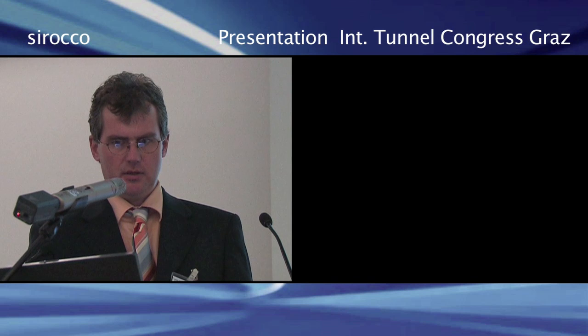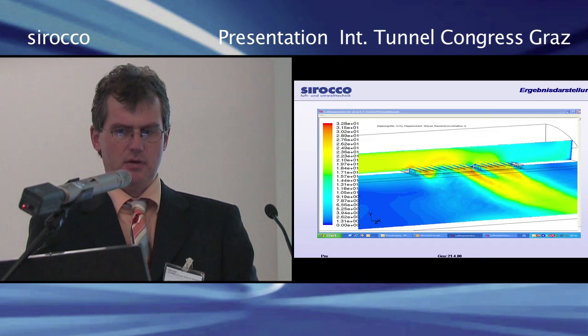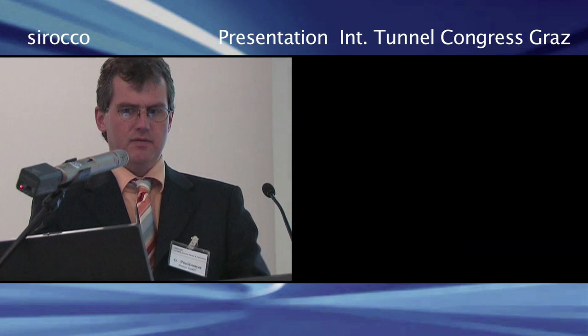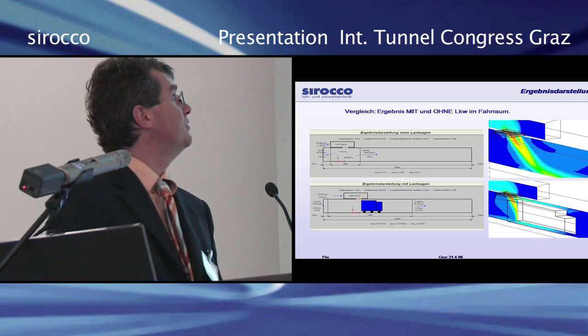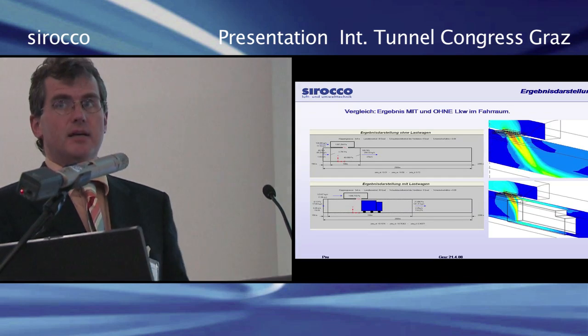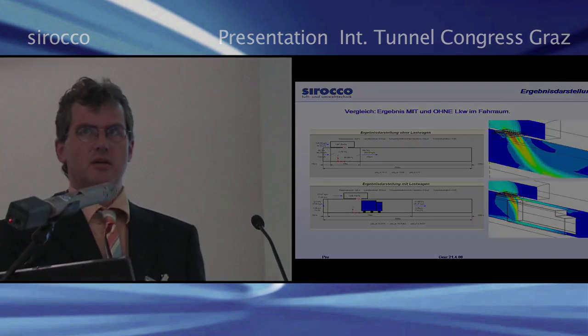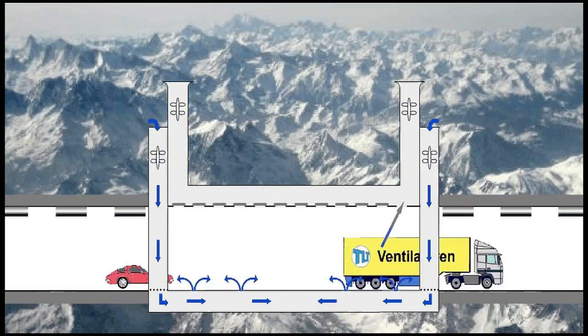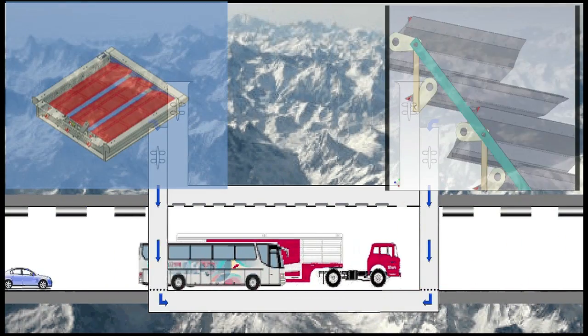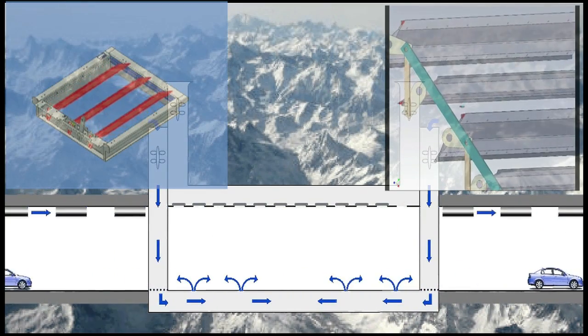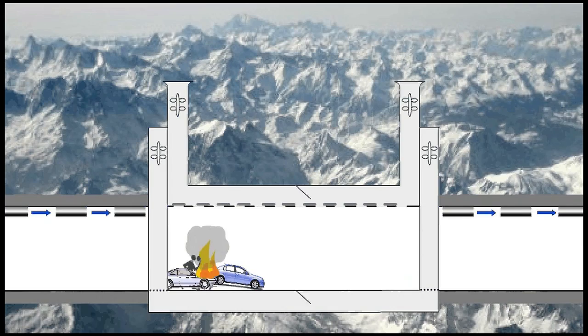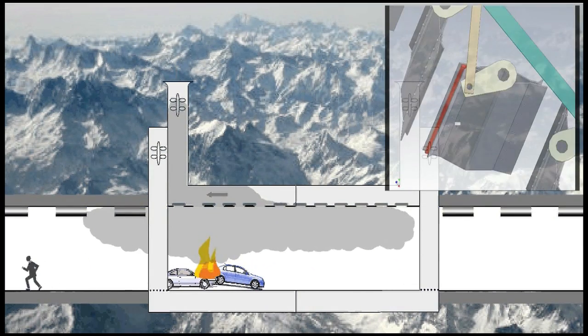Looking at this presentation, you can see the impressive suction effect, which makes the smoke under the extraction blind act like a wall. With these ventilation valves, not only can the basic tunnel ventilation be better managed and controlled, but especially in case of fire, the fumes can be selectively diverted away from the source of the fire.